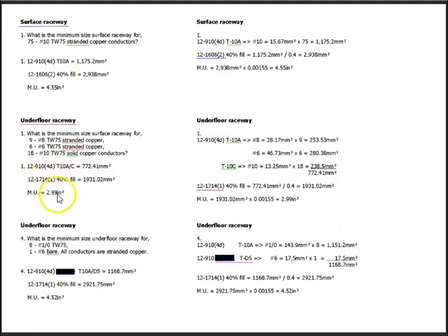Metric unit 2.99. So we just go through more of the same. Table 10A, the number 8s, the number 6s. So we have to apply table 10C here for the number 10s. Add them all up, gives us 772. This number can only be 40% of the total area. So we just take that divided by 0.4.